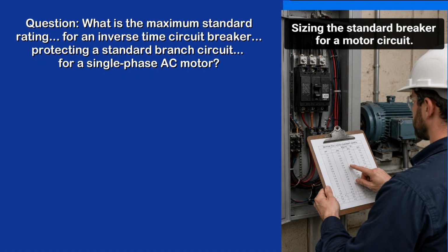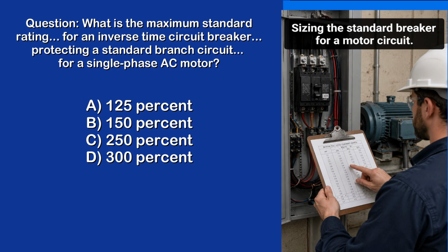Question 6. What is the maximum standard rating for an inverse time circuit breaker protecting a standard branch circuit for a single-phase AC motor? A. 125%. B. 150%. C. 250%. D. 300%. The correct answer is C.